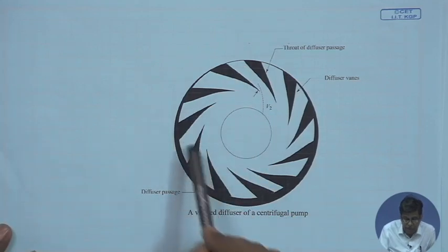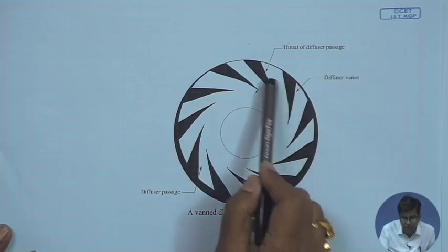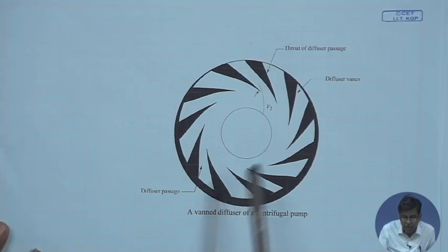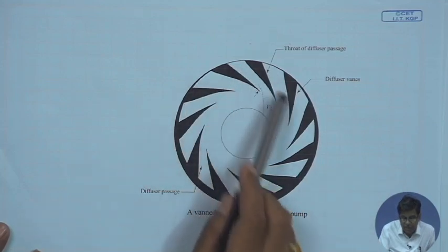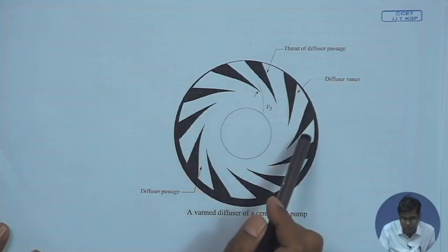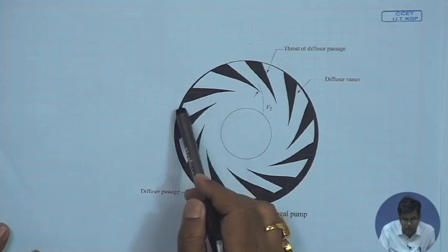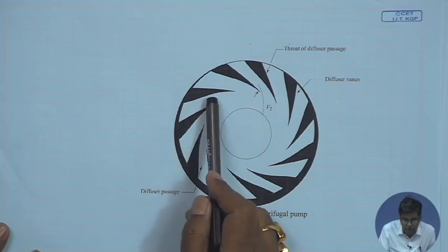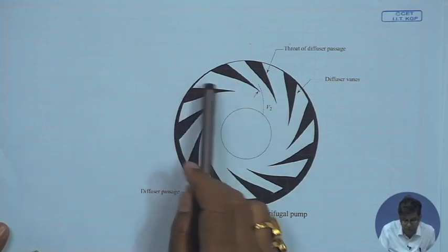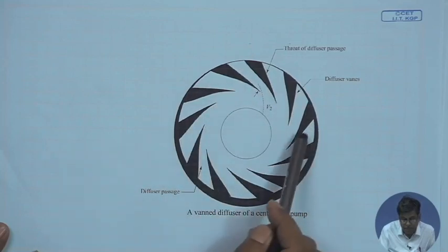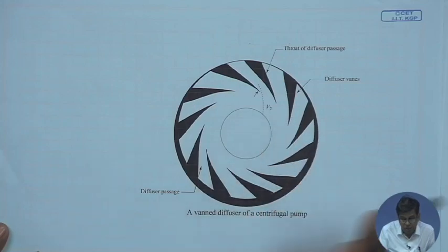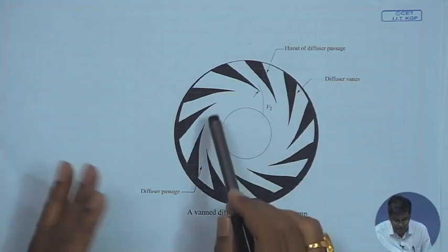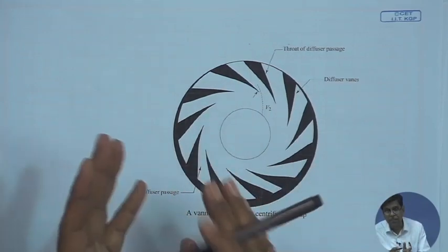Number two is that the number of diffuser vane passages and the number of diffuser vanes is optimized considering two contradicting factors. If the number of diffuser passages or diffuser vanes is more, the process of diffusion — decreasing velocity and increasing pressure — becomes more efficient. But at the same time, if you give more vanes and more channels, frictional losses increase. So a compromise is made between frictional losses and the process of diffusion, and the number of diffuser vanes is optimized.